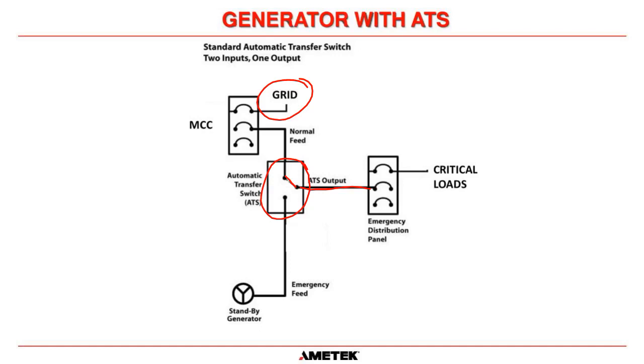And as I said, in this circumstance, it was probably going to be emergency lighting, because if we have a power failure and the grid power fails, the automatic transfer switch will sense that the voltage has disappeared, and it will send a signal, usually to the standby generator, to start. If any of you have any experience with standby generators, the length of time it takes for a standby generator to receive a start signal to the time where it is fully running at frequency and at speed can be around about 30 seconds to a minute.